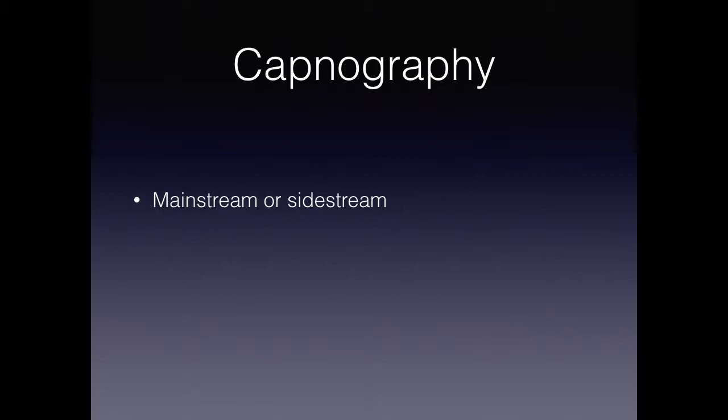Well, first of all, it can be mainstream, meaning we're capturing all of the exhaled gas going through a sensor, or it can be side stream. Most of you have probably seen mainstream a long time ago. It's probably going to make a comeback with volumetric capnography, but mostly you see side stream. And as I say, it can be time-based or it can be volumetric, and some of the most interesting developments now are in volumetric capnography, but it requires different means of measuring this.